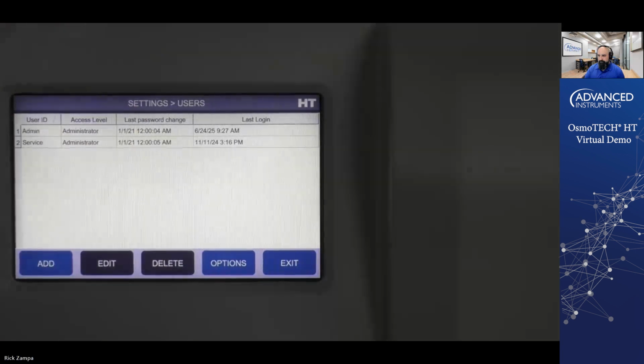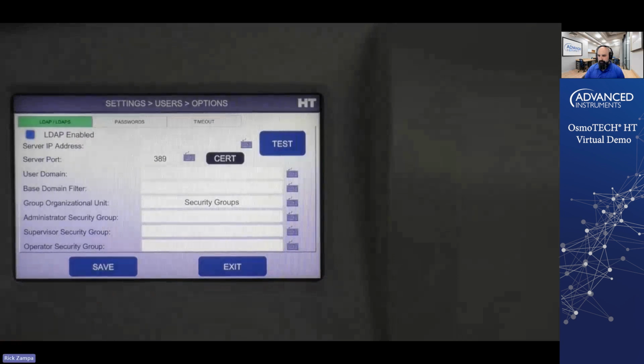So you can load users onto the instrument manually through the touch screen here, or we can go into the options button, and you can load your users through your LDAP system or your Active Directory. This allows your users to use their Windows login or their computer login that they log in with every day as the login on the instrument as well. This reduces the number of passwords and usernames you have to remember and allows for easier access to the instrument. You would enable this here. Your IT department would set up the security groups, put people's usernames and passwords in there, and then they'd have access to the instrument.